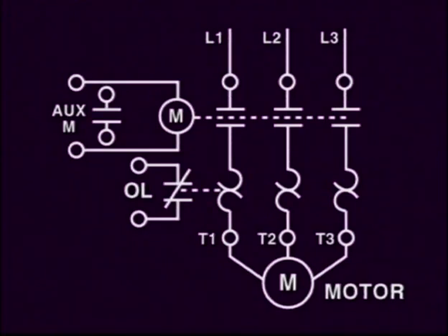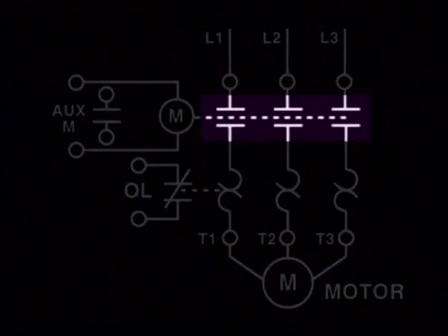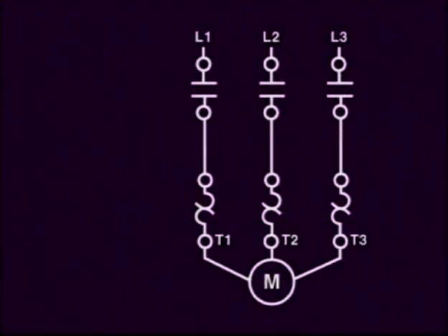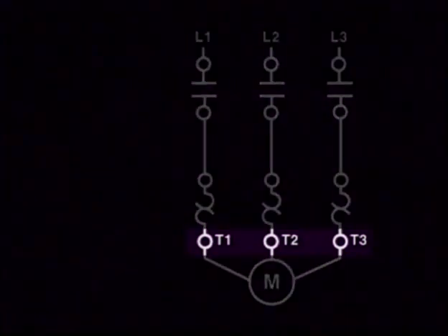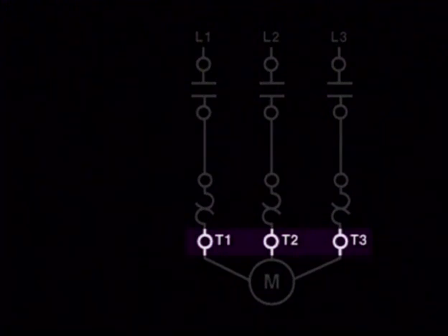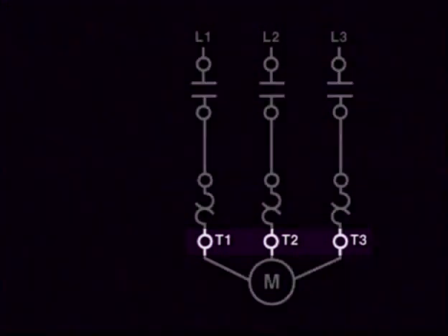The graphic representation of a magnetic starter and its overloads is like this, where the power contacts are shown at the top and the overloads are shown right below. The L1, L2, and L3 lines in a three-phase voltage system will be connected to the top of the starter, while the bottom will go to the motor terminals marked T1, T2, and T3.